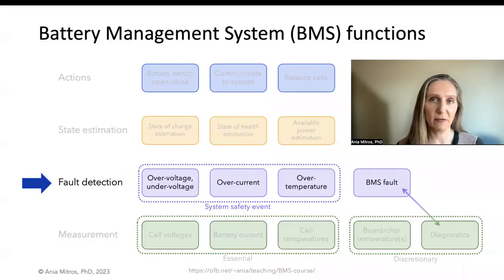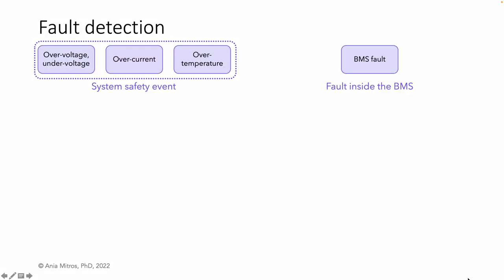Next, we'll talk about fault detection. Fault detection falls into two categories: system safety events, which are risky in themselves, and BMS faults, which indicate that our BMS has a problem. That is, we can't fully trust what the BMS is reporting or doing. When a system safety event occurs, we must take action. Our battery system is in an unsafe region of operation.